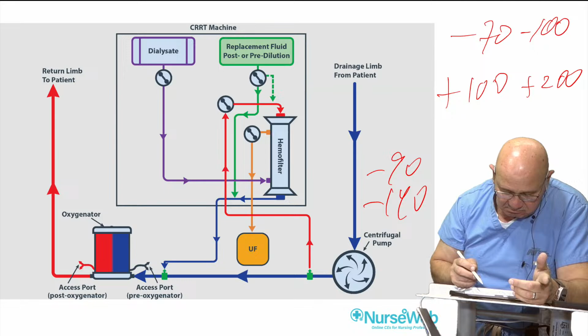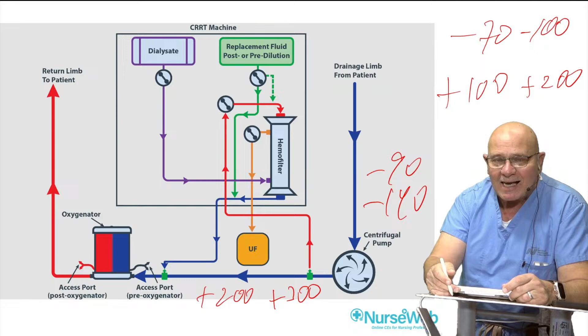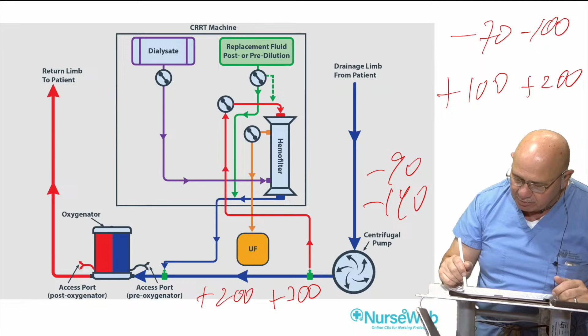So when you hook it into an ECMO circuit where this might be -90, it could be -140. It could be anything like that. This can be +200, it could be positive 300. You could easily see where these pressures within the ECMO circuit are hostile to an overall CRRT or CVVH circuit. Here is yet another way to do this, where you're taking your access from the patient return limb of your ECMO with a roller pump controlling it, going in and going back to the negative side. Again, you're going to have the same problem.